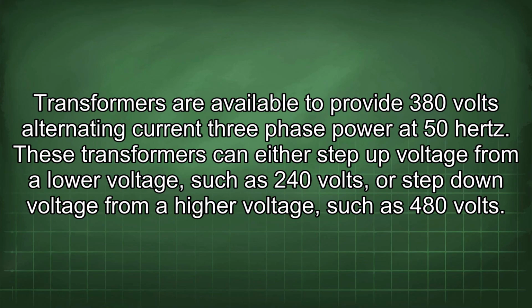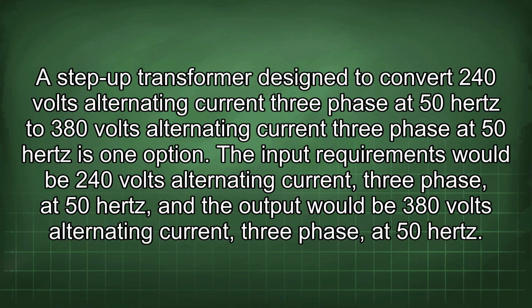Transformers are available to provide 380 volts alternating current 3-phase power at 50 Hz. These transformers can either step up voltage from a low voltage, such as 240 volts, or step down voltage from a higher voltage, such as 480 volts. A step-up transformer designed to convert 240 volts alternating current 3-phase at 50 Hz to 380 volts alternating current 3-phase at 50 Hz is one option. The input requirements would be 240 volts alternating current 3-phase at 50 Hz, and the output would be 380 volts alternating current 3-phase at 50 Hz.